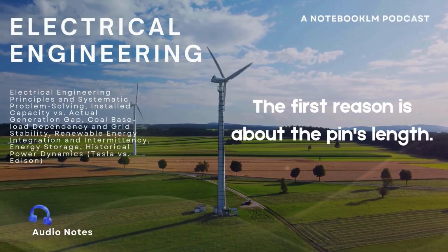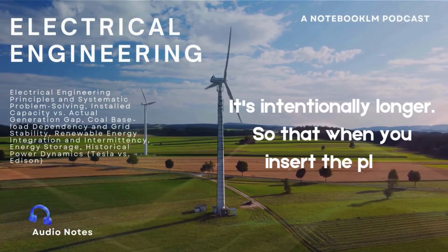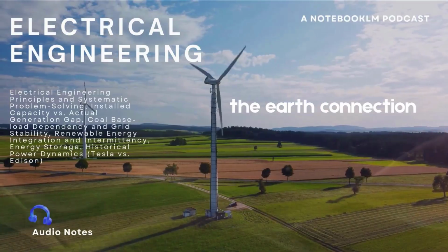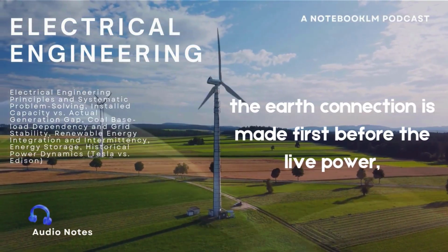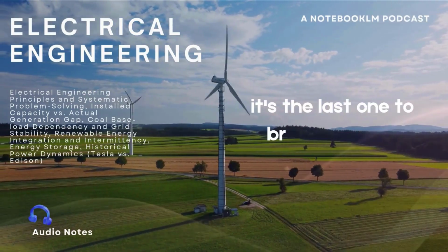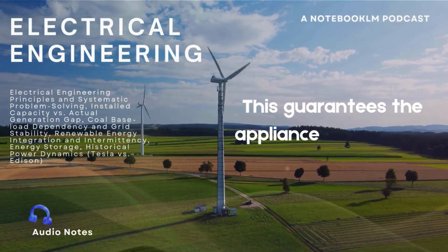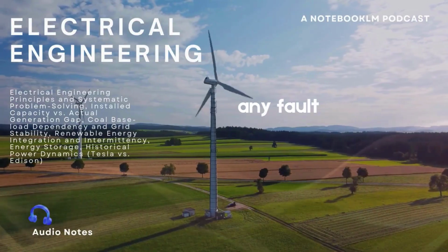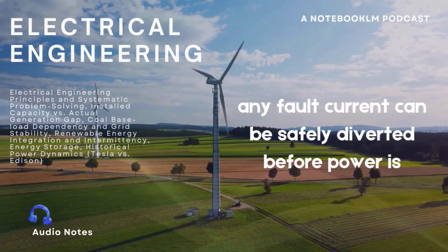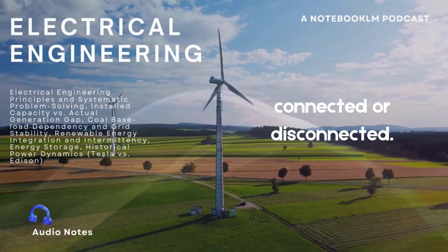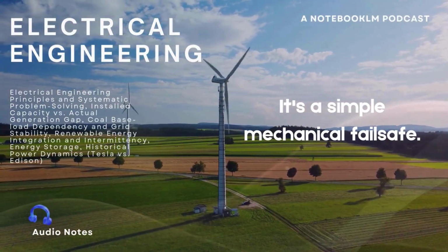The first reason is about the pin's length. It's intentionally longer so that when you insert the plug, the earth connection is made first. Before the live power. Before the live power. And when you pull the plug out, it's the last one to break contact. This guarantees the appliance is grounded, and any fault current can be safely diverted before power is connected or disconnected. It's a simple mechanical failsafe.